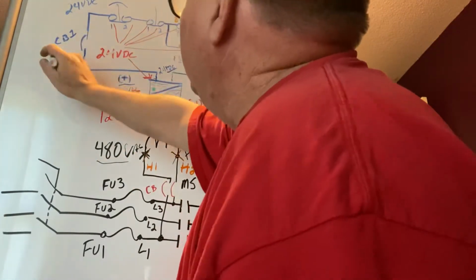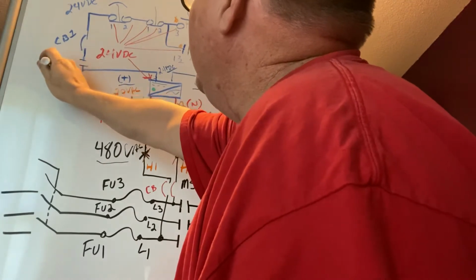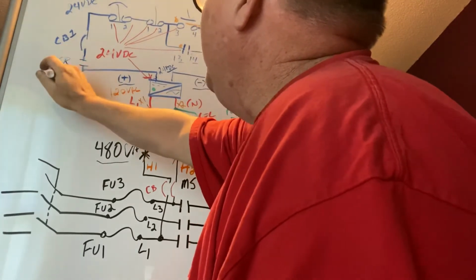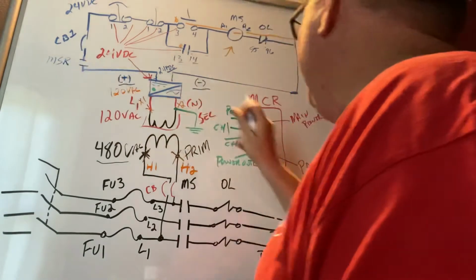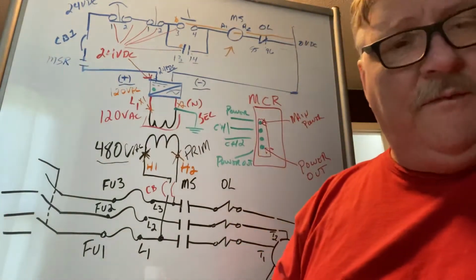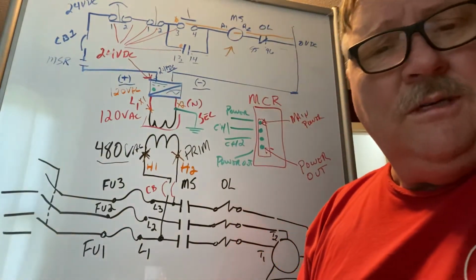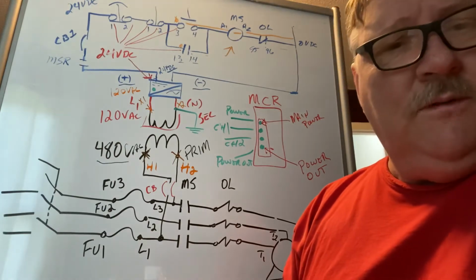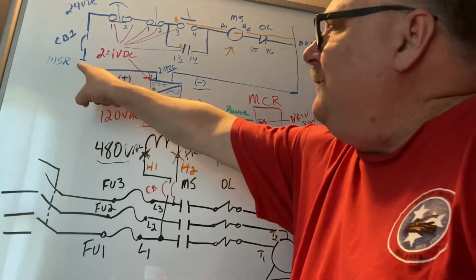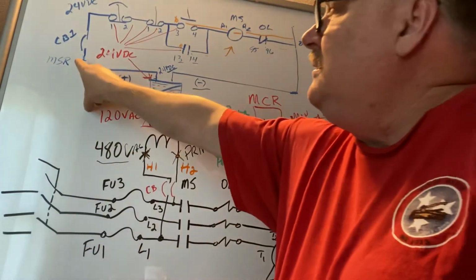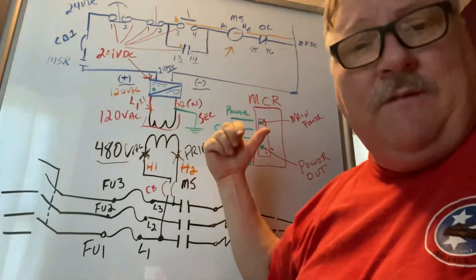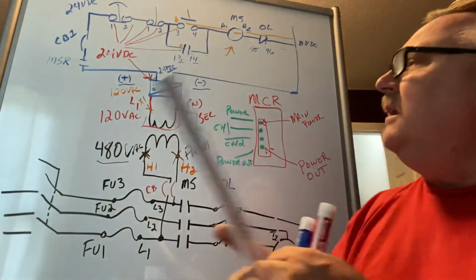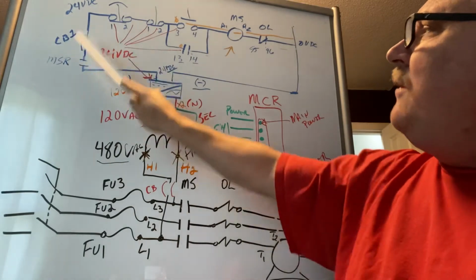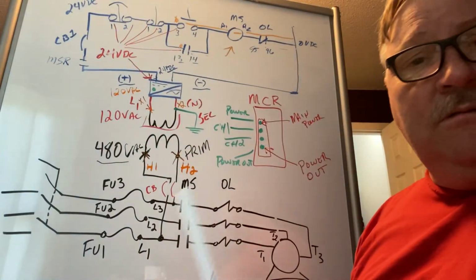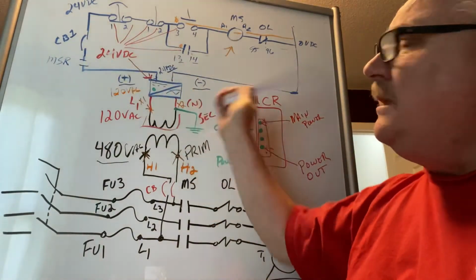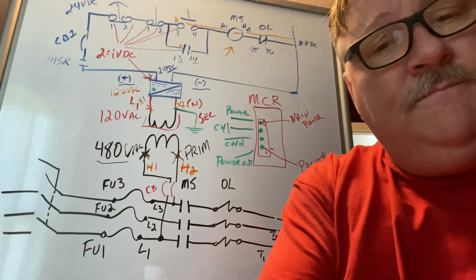Okay? And typically, to make an adjustment on this, you'll see in a drawing a normally open contact, and it will be MSR and whatever the terminal numbers are going to be on that. It can be an S21, it can be an S13, 14, whatever the case may be. But if this isn't on, then that's going to be open. When your safety device has been done, this will close and allow the 24 volts to go through your circuit. If this gets violated, it opens that and you get nothing in your control circuit. Okay?